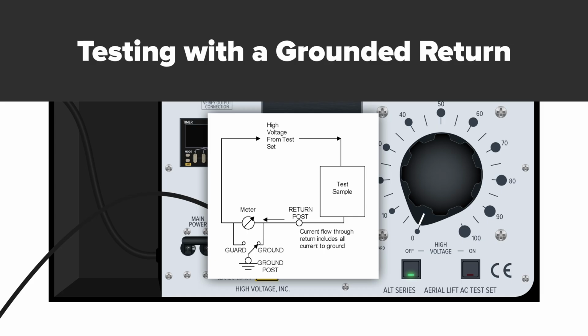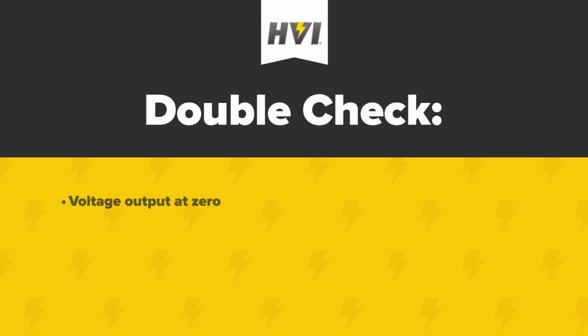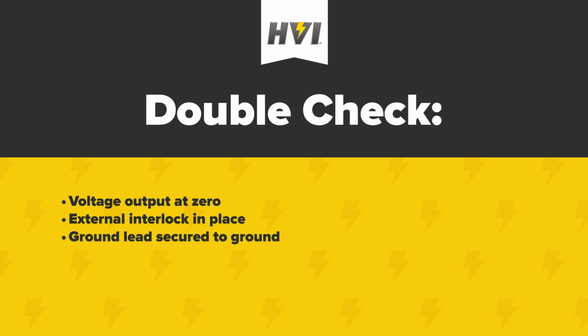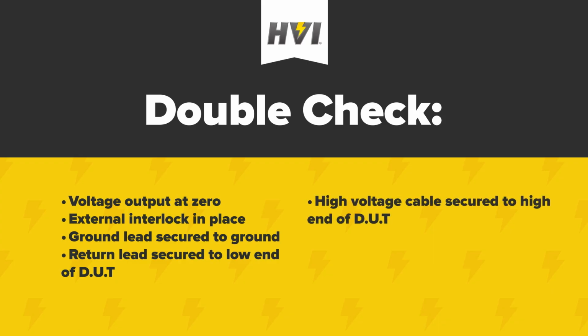Testing with a grounded return. Once set up, double-check that the voltage output setting is in 0 position and that the interlock key is secured in the external interlock. Check that the ground lead is securely connected to a grounding element. Check that the return lead is connected to the low side of the DUT, and that the high voltage output cable is connected to the high side.